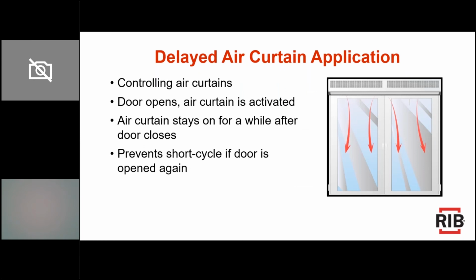Also, delayed air curtain application. I don't know if you've ever walked into a convenience store or the entrance of a sliding glass door or something, but those fans that blow your hair down when you walk in, those are air curtains, and our delay relays are perfect for that, to prevent short cycling of those air curtains. So if somebody walks in and closes the door, it could wait about 30 seconds so that if another person walks in 15 seconds later, it's still on and running.